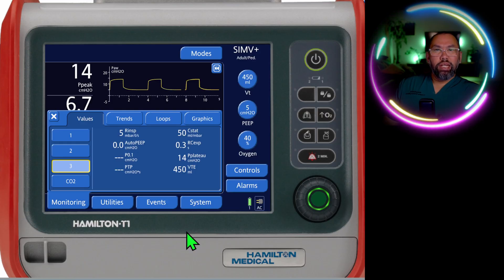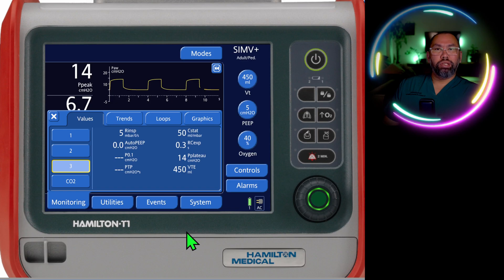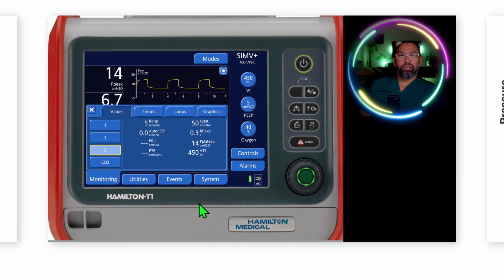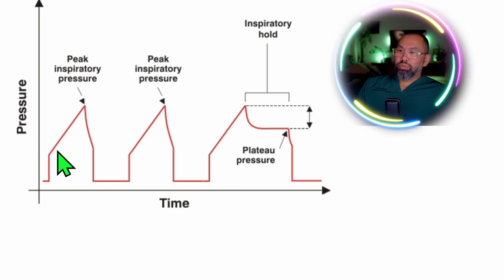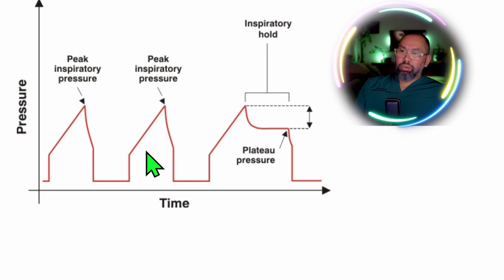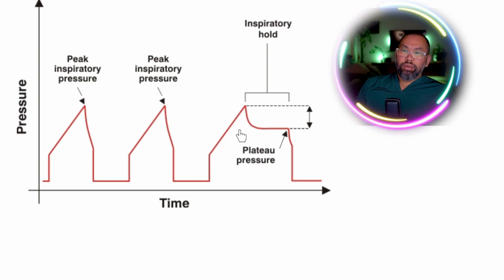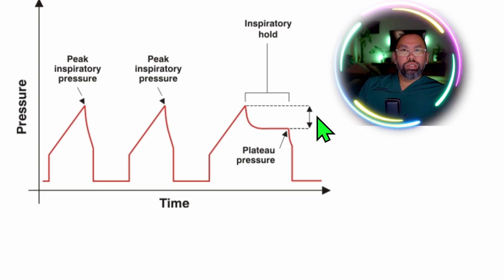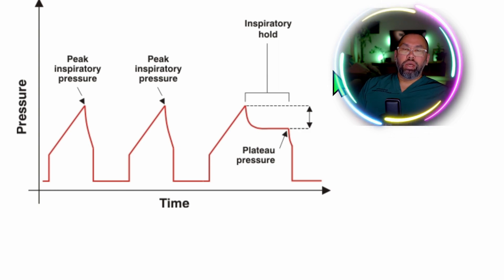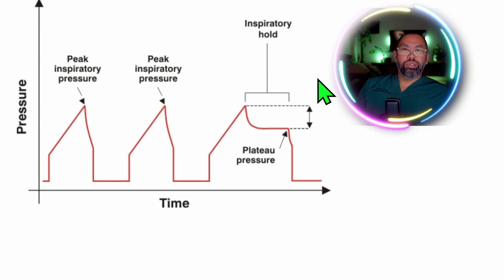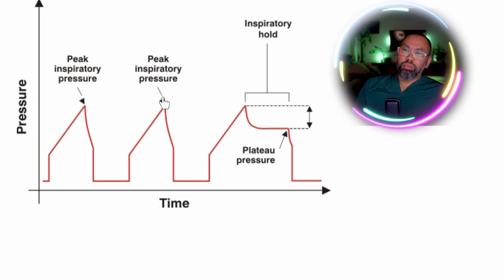Some of you might be saying you need to do an inspiratory hold first before you get a plateau pressure — and you're right. So here we have a pressure scalar, pressure over time, with a couple of pressure waveforms and a couple of mandatory volume control breaths. This breath here, we've performed an inspiratory hold. The reason you need an inspiratory hold is that any time there's gas flowing through the system — the system being ventilator, tubing, tracheal tube, airways — that flow of gas exerts a force, and that force exerts a pressure on the system. The pressure on the system is your peak inspiratory pressure.